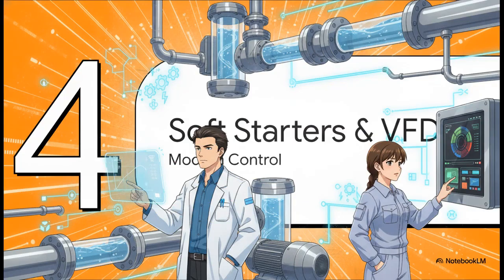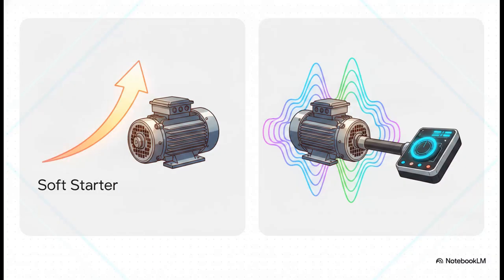Next up, Section 4, Soft Starters and VFDs. Tech has come a long way, and modern pump stations are all about ultimate control. Let's compare two of the smartest tools we have. First, the soft starter. Its main job is to gradually increase the voltage, giving the motor a super smooth start and cutting down on mechanical wear and tear. But the VFD, or variable frequency drive, takes things to a whole new level. Instead of just tweaking voltage, a VFD actually changes the frequency of the power supply. This means you can completely control the exact speed of the motor. For maintaining precise water pressure and saving a ton of energy, VFDs are a real game changer.